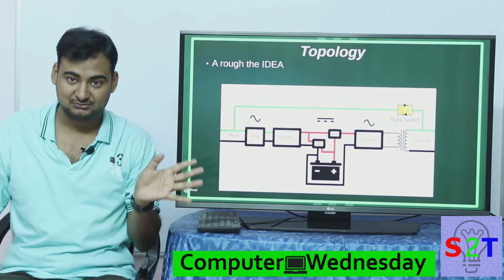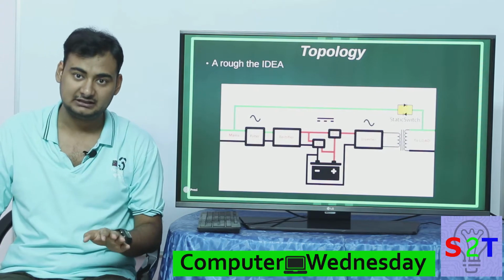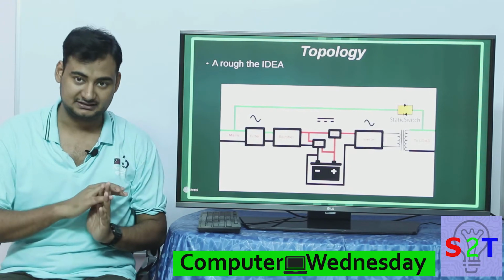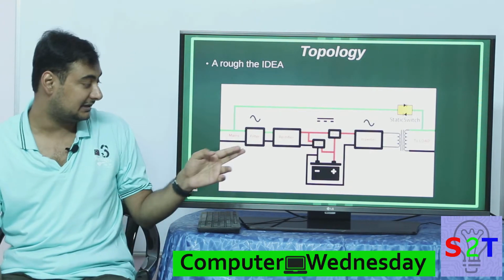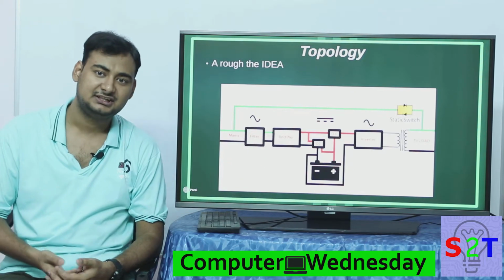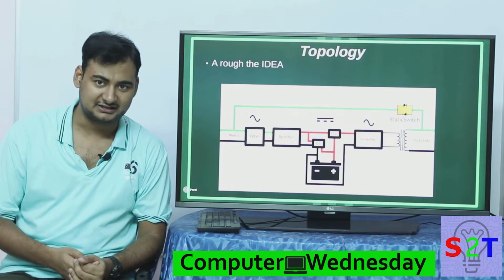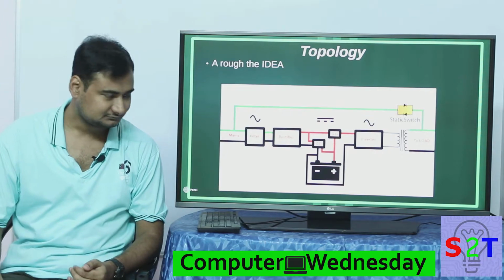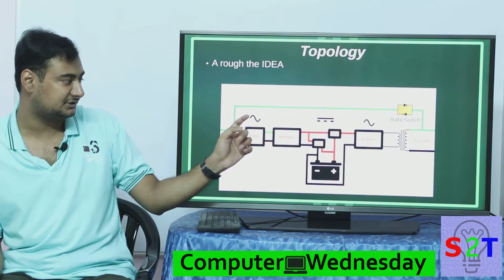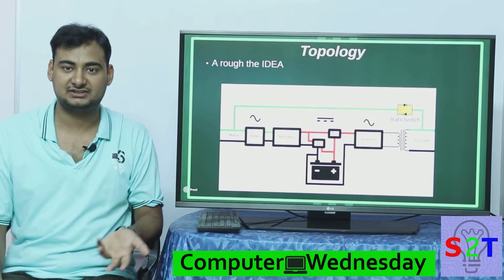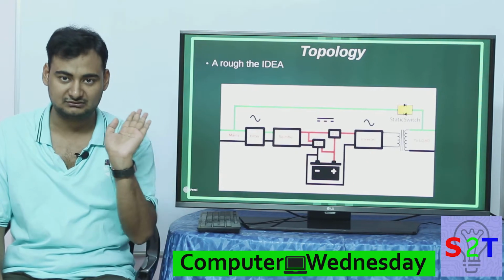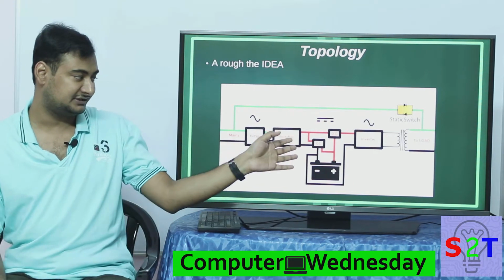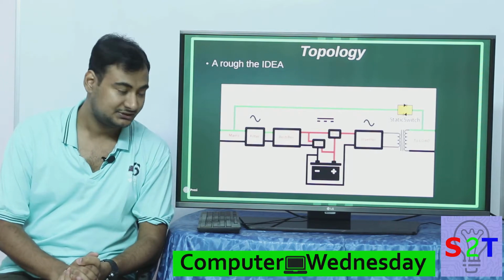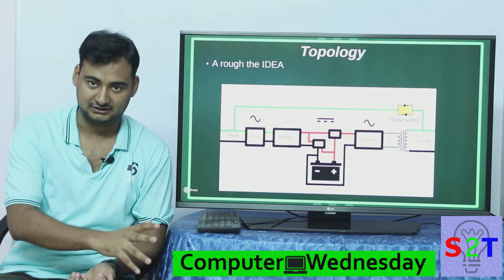So even if the UPS fails, you won't have a complete failure. All it will do is simply bypass to mains. Or sometimes they could bypass after the filter, because generally filters don't break down that easily. So they can directly bridge from here, or sometimes there could be just a manual switch: if your UPS goes down, you flip that switch and you can disconnect the UPS and maintain it. So this is the whole process for it.